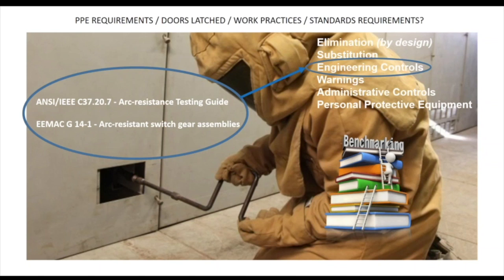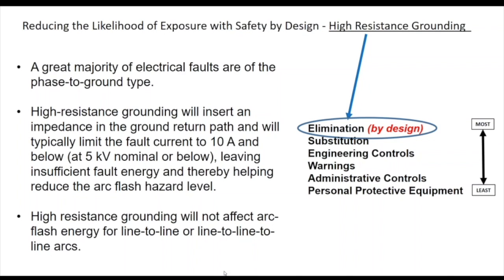So I really want you to think about what work practices you are going to have going forward. Can you put good electrical design in place to reduce the risks? And you have to do that in the risk assessment phase and the design phase. Just as another example, to reduce the likelihood of exposure with safety by design, high resistance grounding. A great majority of electrical faults are the phase to ground fault. They really are. Even in a 600 volt motor control center starter, certainly for people who use a non-insulated screwdriver, it goes single phase to ground. If it goes single phase to ground, it will often propagate, phase to phase to phase to ground, and it's a very significant arc flash, and people get hurt, and certainly on higher voltage equipment as well.